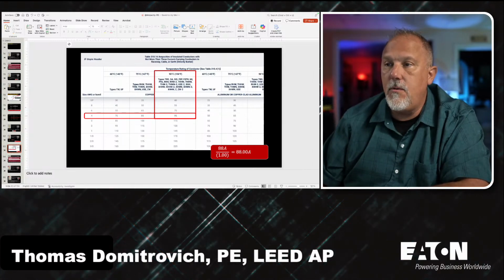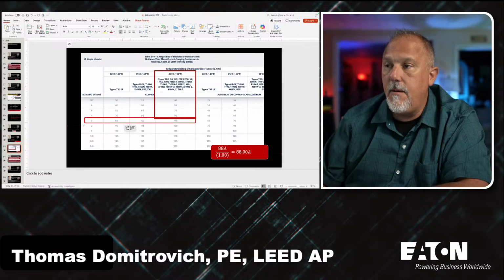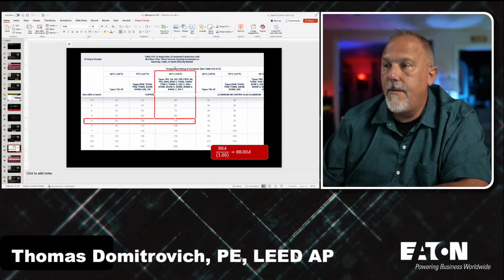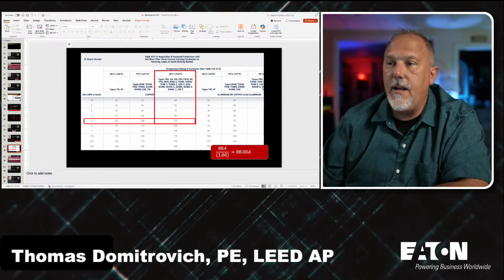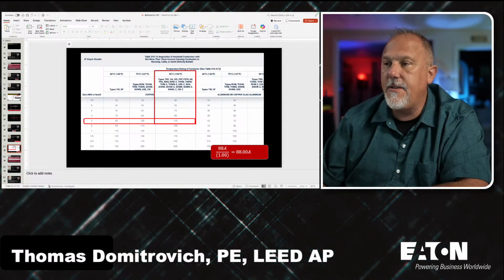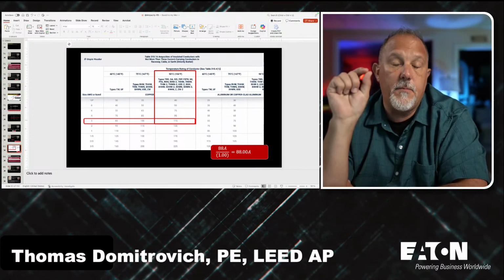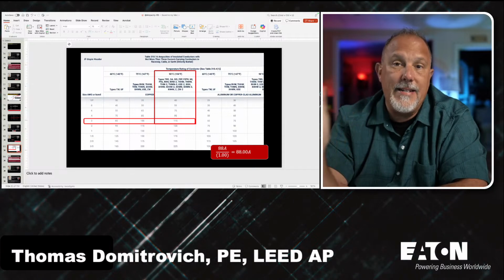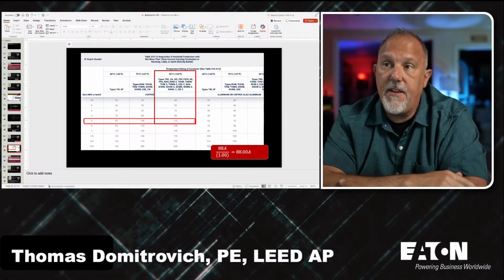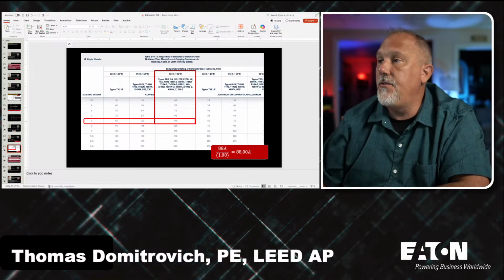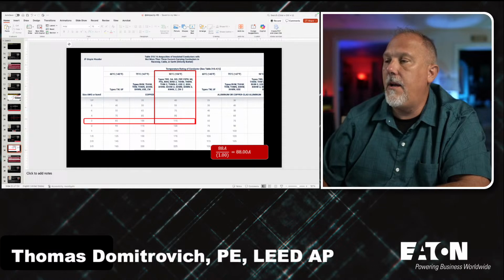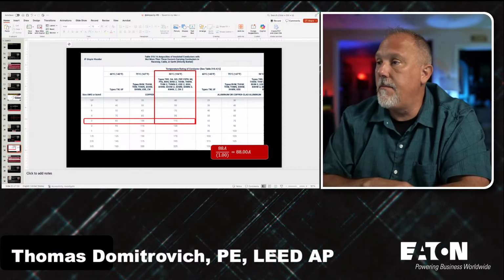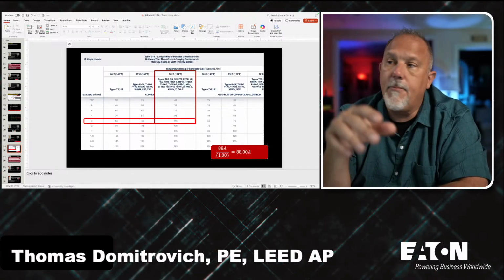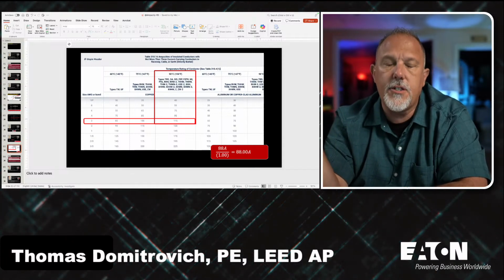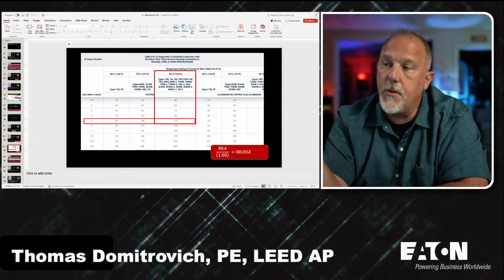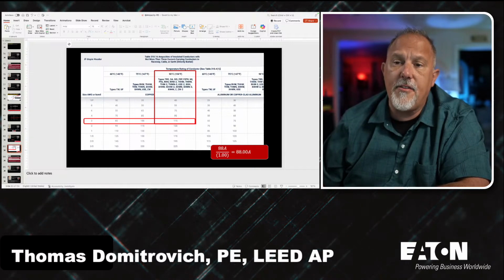Now if I come into the table and go to the 90 C column, I am right here at 115 amps based upon the 90 C column. For that conductor, based upon those conditions of use and a continuous load, I'm at a number 3 gauge copper conductor. I don't have aluminum or copper clad aluminum here, but we'll stick with copper for now. You can pick a different number, but you get the fundamental principle.